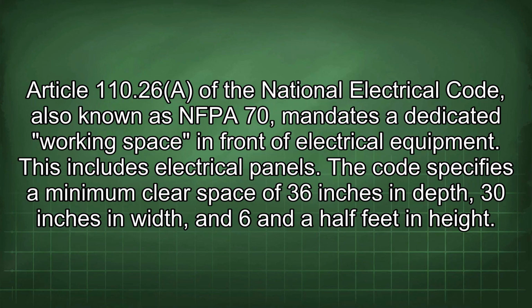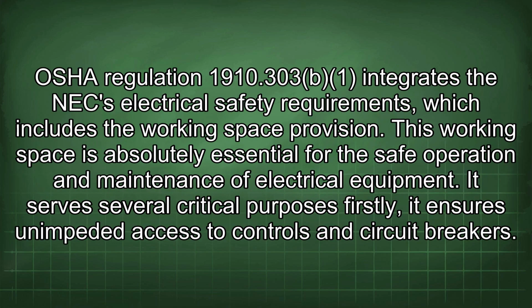Article 110.26 of the National Electrical Code, also known as NFPA 70, mandates a dedicated working space in front of electrical equipment. This includes electrical panels. The code specifies a minimum clear space of 36 inches in depth, 30 inches in width, and 6.5 feet in height. OSHA Regulation 1910.303 integrates the NEC electrical safety requirements, which includes the working space provision. This working space is absolutely essential for the safe operation and maintenance of electrical equipment.